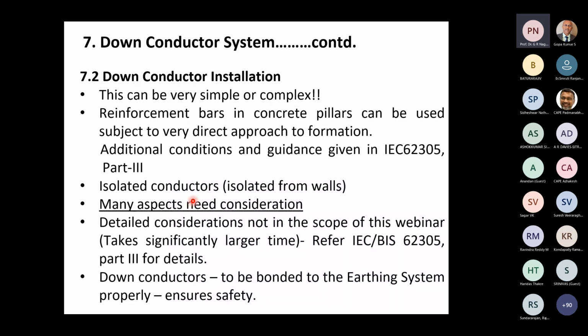Now, sometimes the down conductors have to be isolated from the walls to avoid current flowing through the concrete, and then the isolation has to be insulated isolation. These must also be barricaded so that no person comes into contact with them externally. So many aspects need consideration in the design of the down conductor system. As I mentioned a little earlier, the down conductor design is the most complex in many cases.